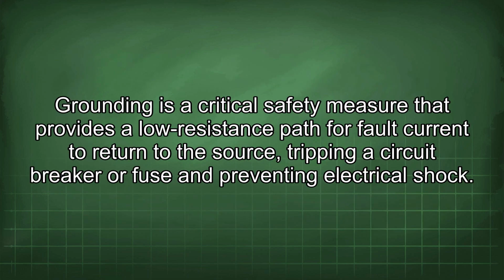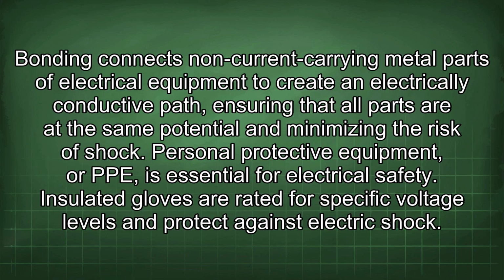Grounding is a critical safety measure that provides a low resistance path for fault current to return to the source, tripping a circuit breaker or fuse and preventing electrical shock. Bonding connects non-current carrying metal parts of electrical equipment to create an electrically conductive path, ensuring that all parts are at the same potential and minimizing the risk of shock.